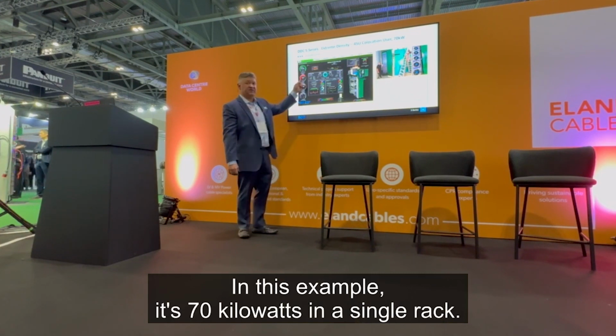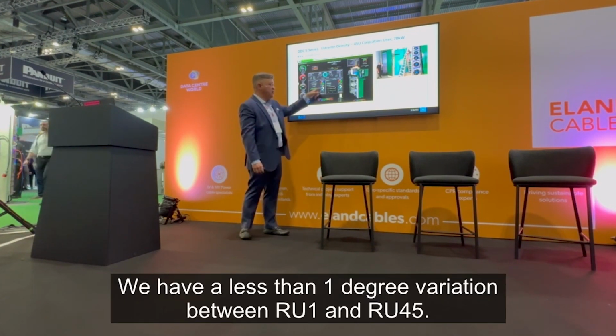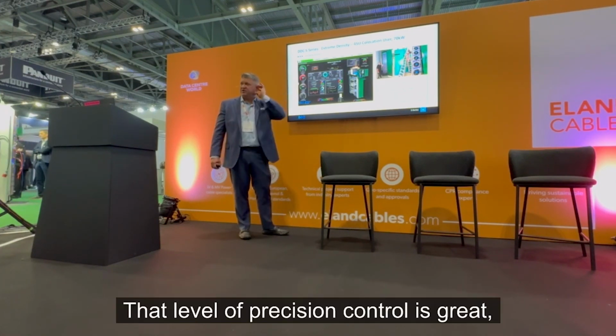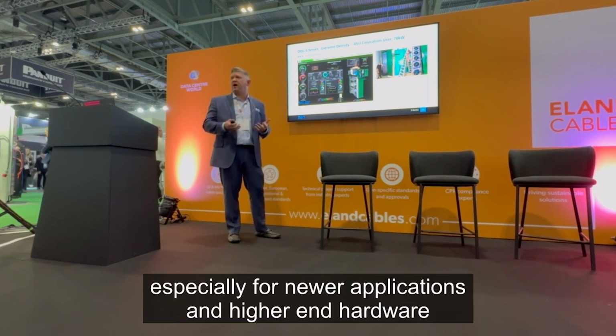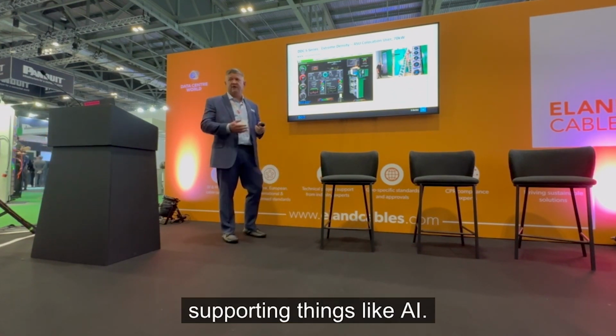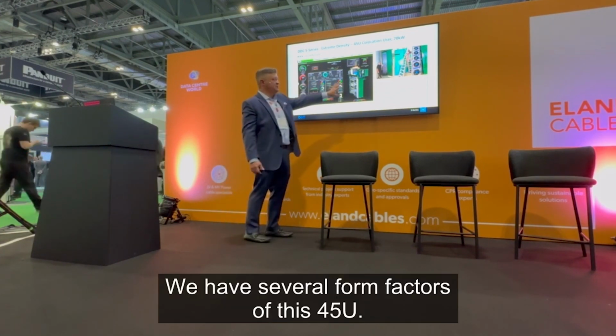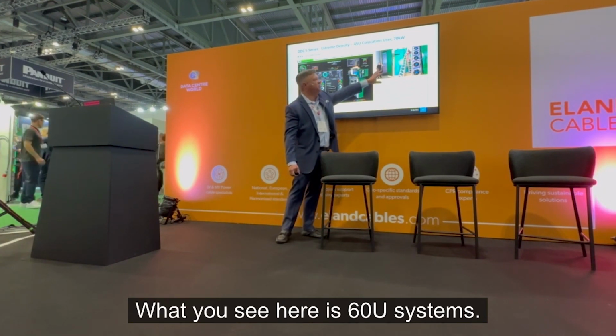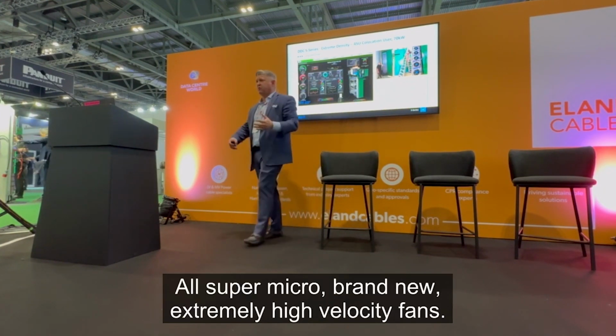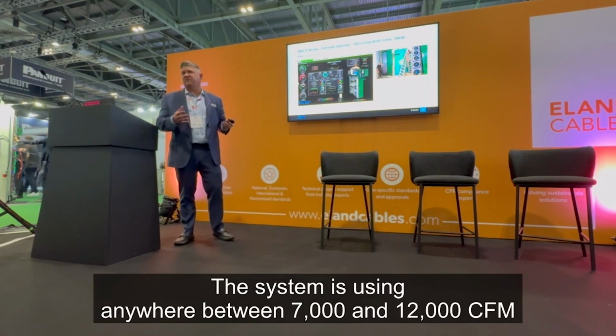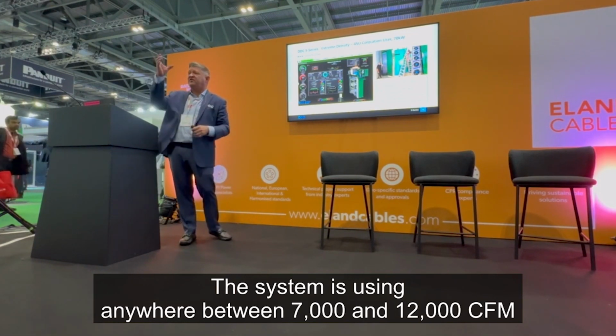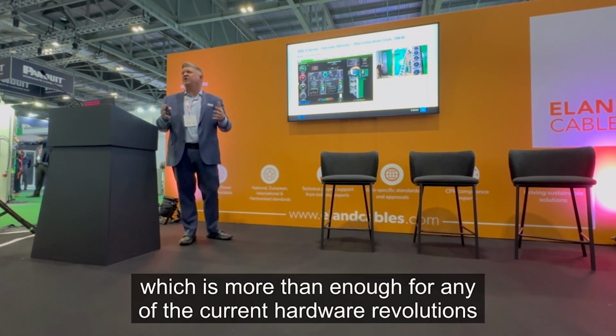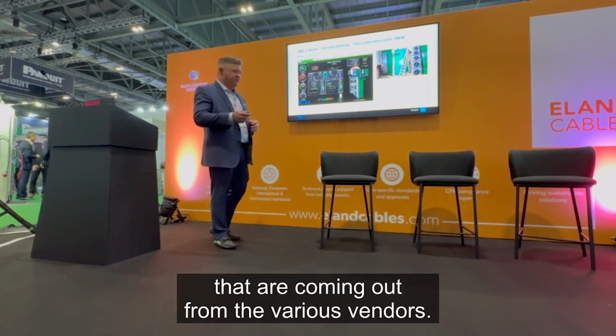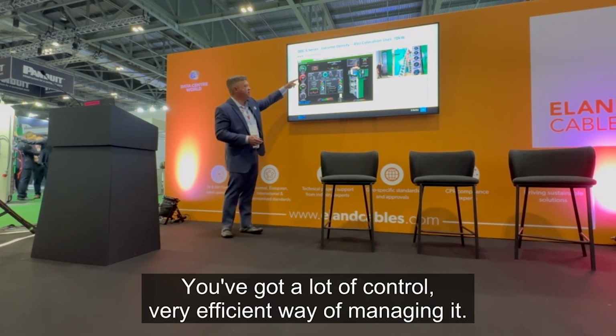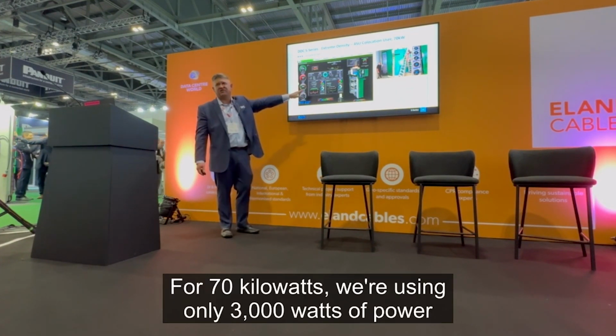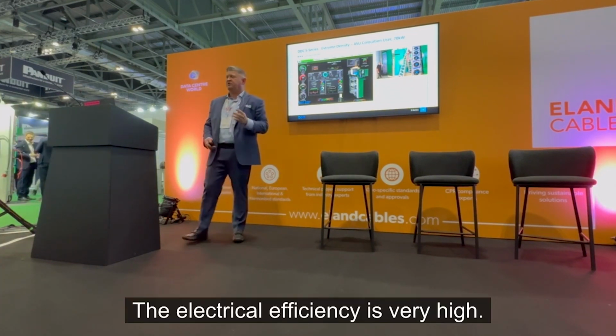And in this example, it's 70 kilowatts in a single rack. We have less than 1 degree variation between RU1 and RU45. That level of precision control is great, especially for newer applications and higher end hardware that's supporting things like AI. We have several form factors: the 45U, and you see here 60U systems. Those are 9 different systems, all Supermicro, brand new, with extremely high velocity fans. The system is producing anywhere between 7,000 and 12,000 CFM on the front side supply, which is more than enough for any of the current hardware revolutions coming out from the various vendors. So we've got a lot of control, a very efficient way of managing it. And for 70 kilowatts, we're using only 2,000 watts of power to cool and manage that workload. So the electrical efficiency is very high.